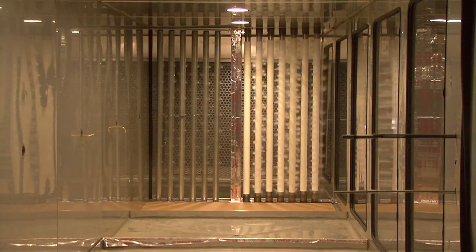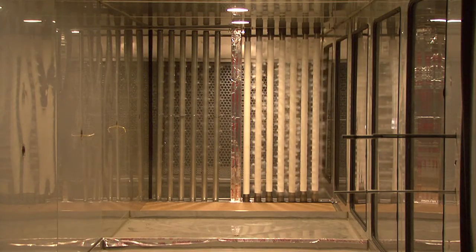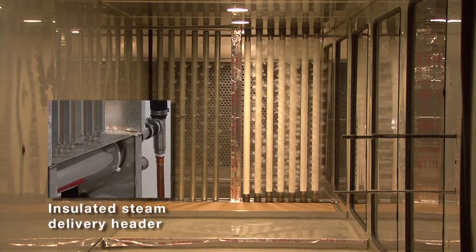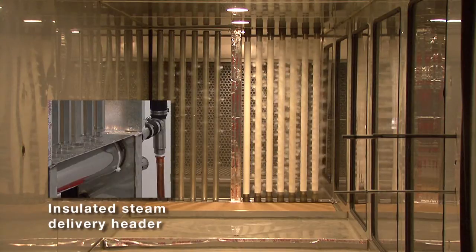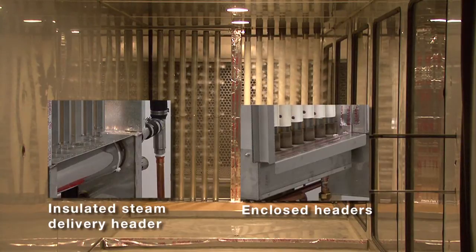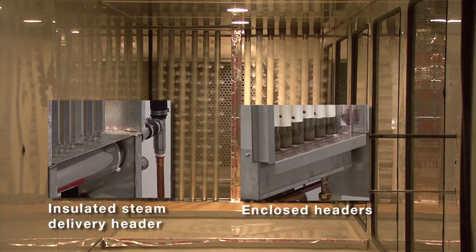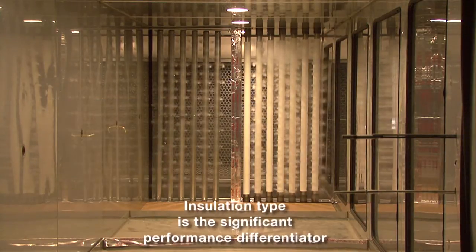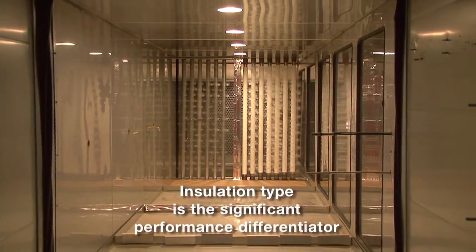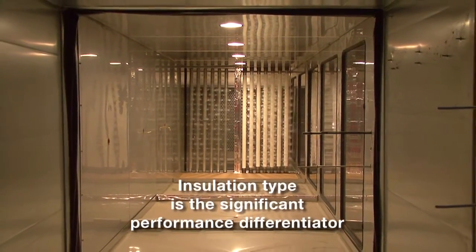The two dispersion assemblies are very similar in construction except the dispersion assembly on the left has an optional insulated steam delivery header, and the dispersion assembly on the right has factory standard enclosures around the steam delivery and condensate drain headers, and also has an extra inactive tube that functions as a header drain. However, the significant difference impacting efficiency between these two dispersion assemblies is their dispersion tube insulating technology.